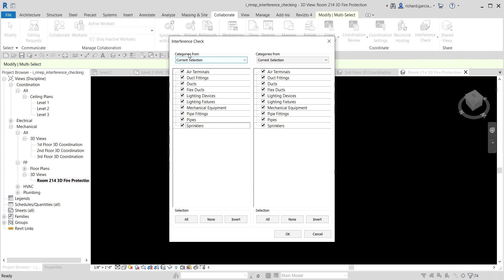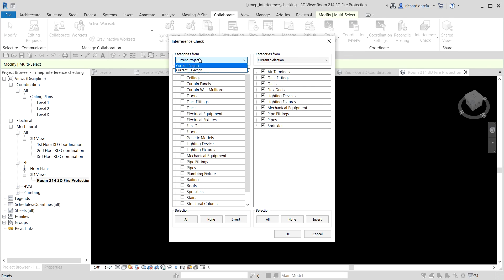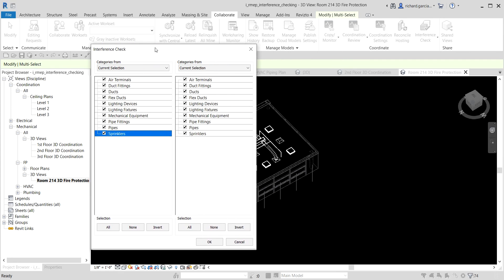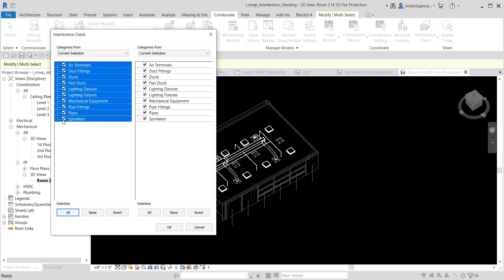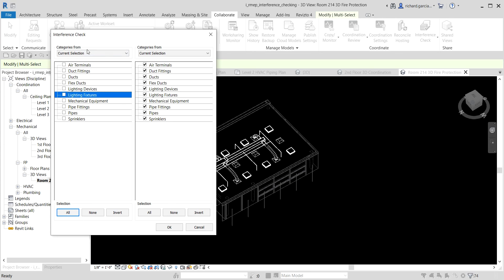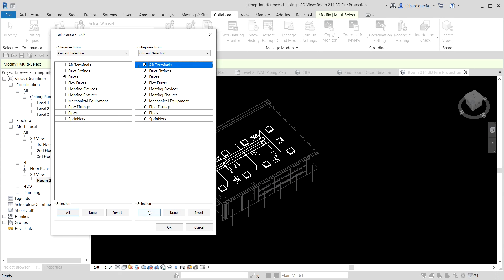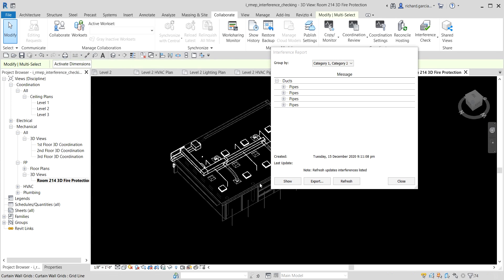After selecting objects, go to Collaborate > Interference Check > Run Interference Check. In the dialog, the 'From' dropdown now shows a 'Current Selection' option in addition to 'Current Project.' Current Selection means it will only show elements you have selected in your view. Let's check clashes between ducts and pipes — select ducts on one side and pipes on the other, then click OK.